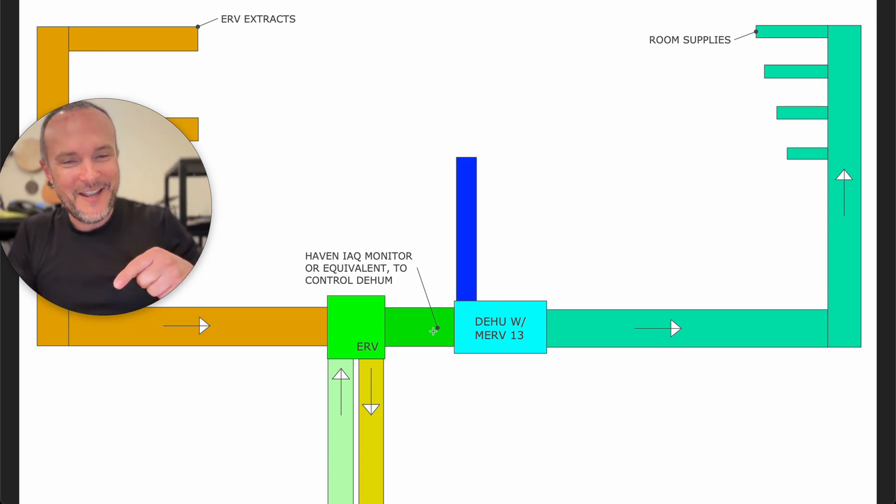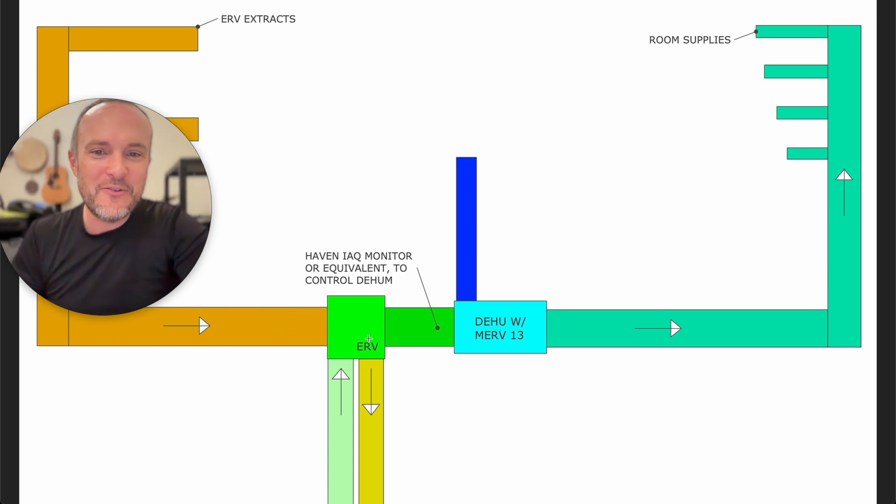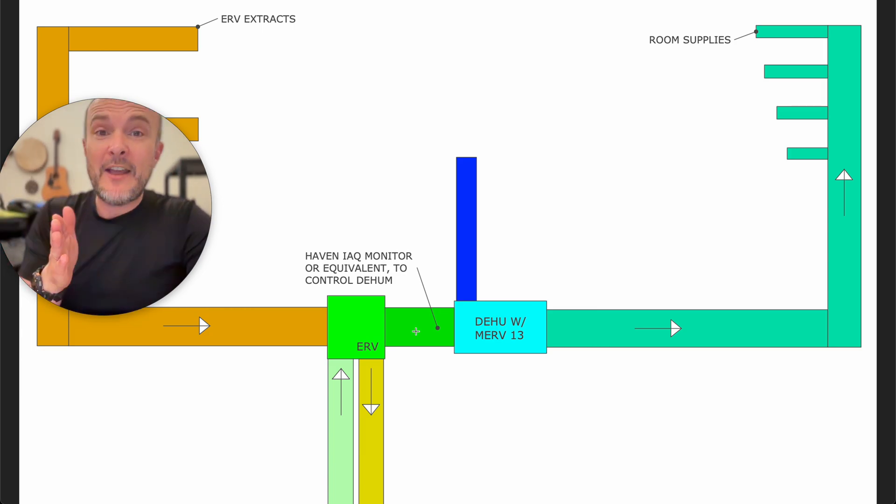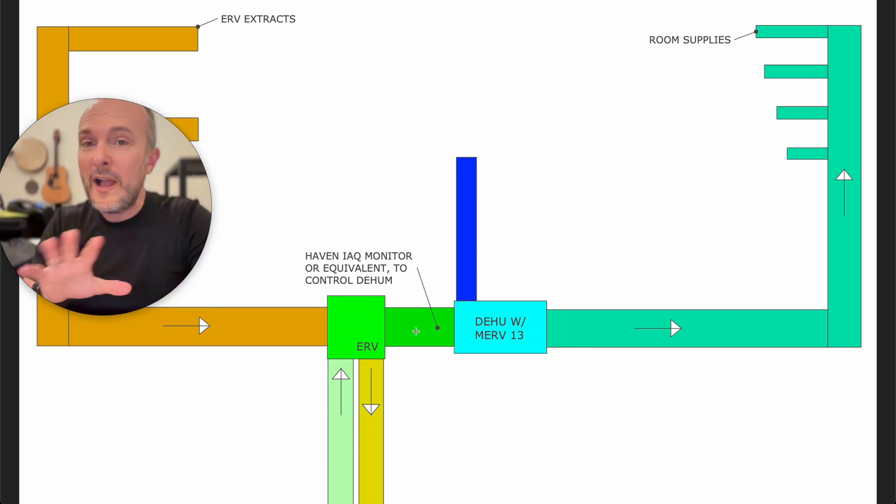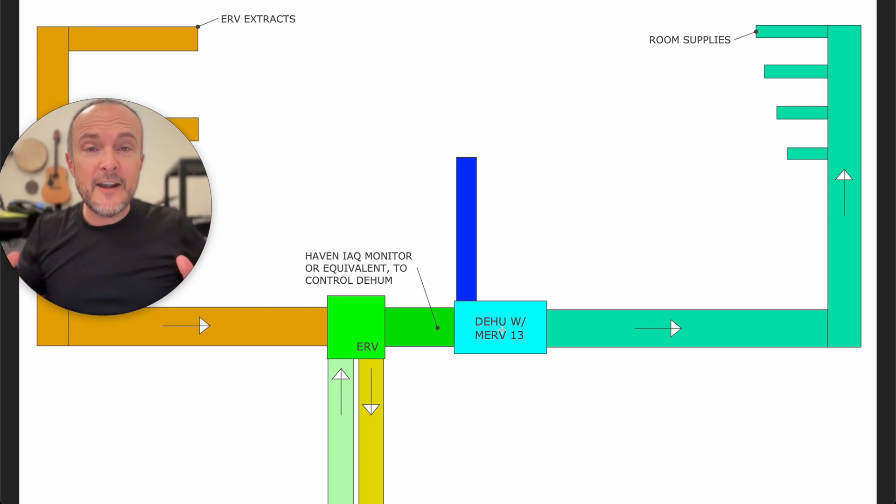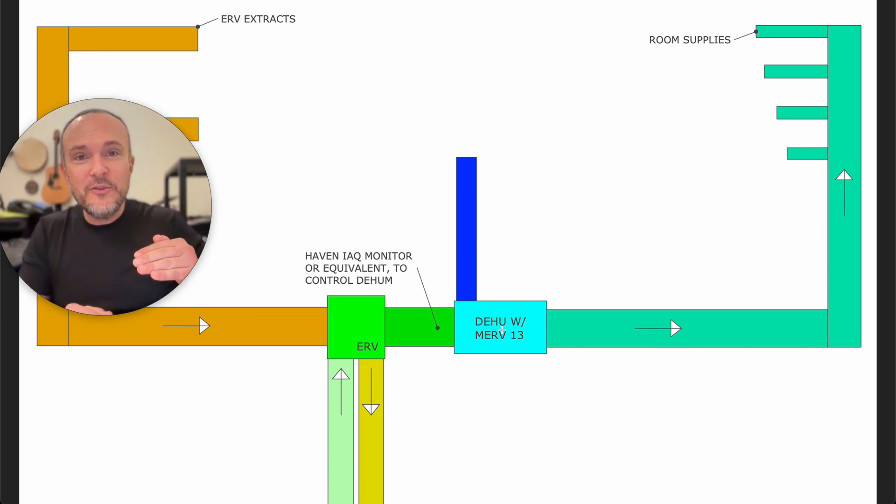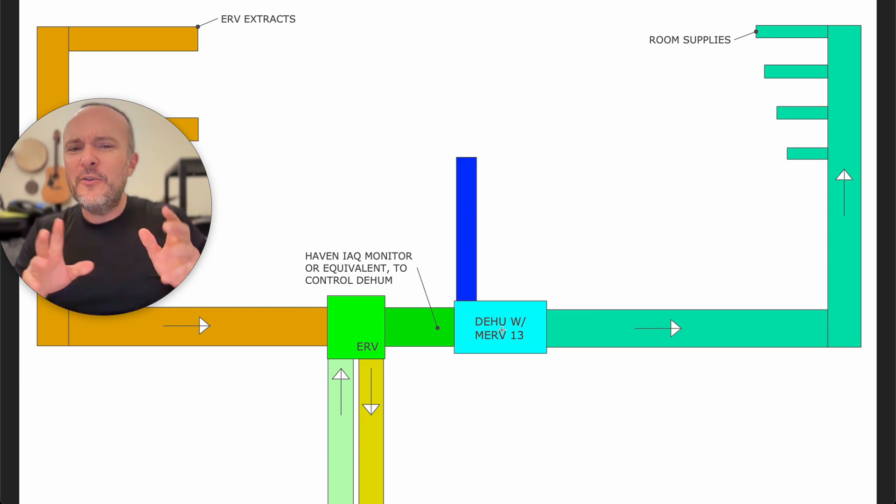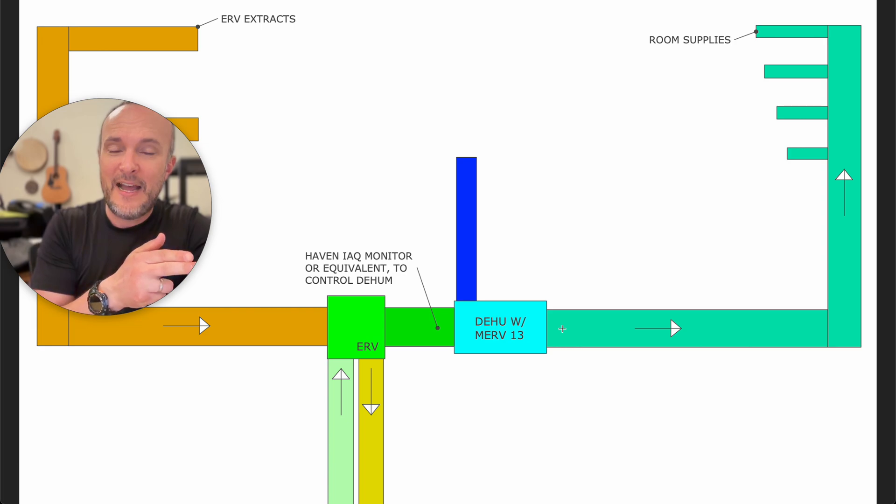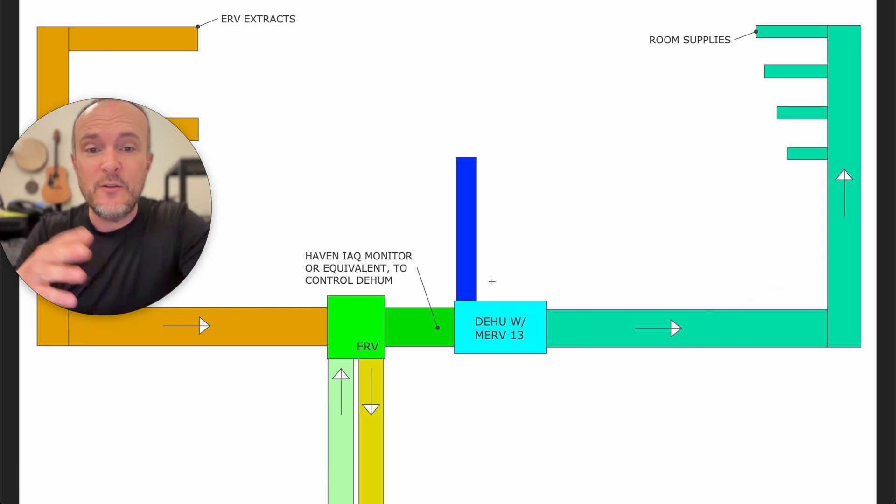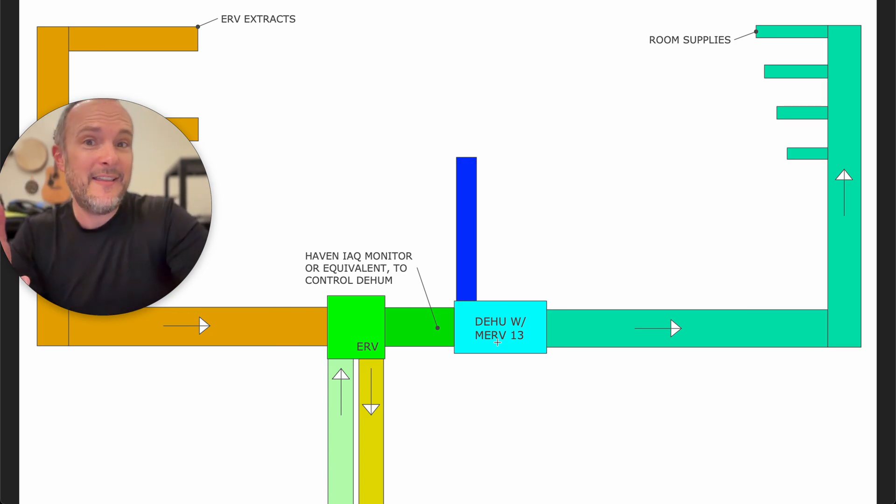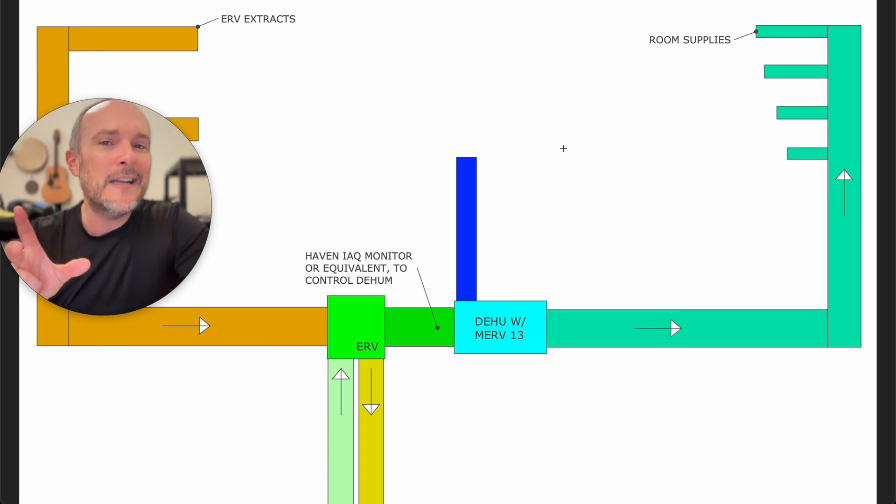Number two is in the winter time when it's snowing outside and it's 30 degrees and 100% relative humidity comes in through this ERV core and let's say it warms up to 45 degrees or whatever it is, but it's at 55% relative humidity. It's still—that's super dry, because relative is relative to the temperature. The dehumidifier is going to be like, 'Oh my god, 55% relative humidity, I need to dry.' And that's not true because it's already super dry. All we need to do is warm the air, which is already happening in this system, and everything will be fine. So once the humidity makes it past this in that summertime example and it goes into the house, now it's too late. We can't actually have the dehumidifier dry this at all anymore because it already got past it and it's in the house and now it's just cycling in here.